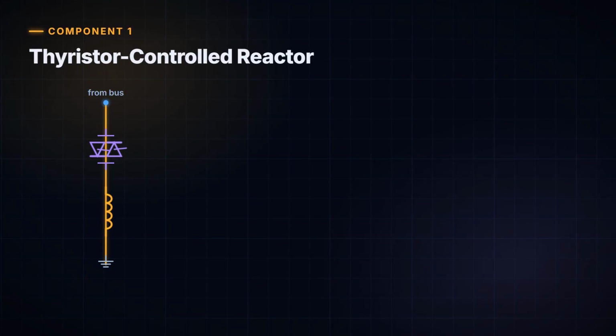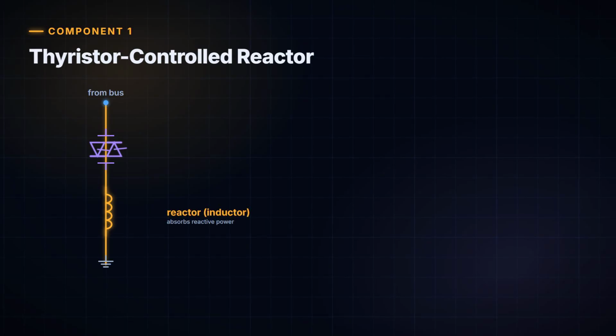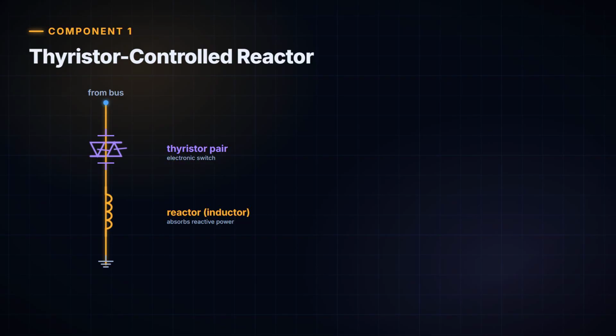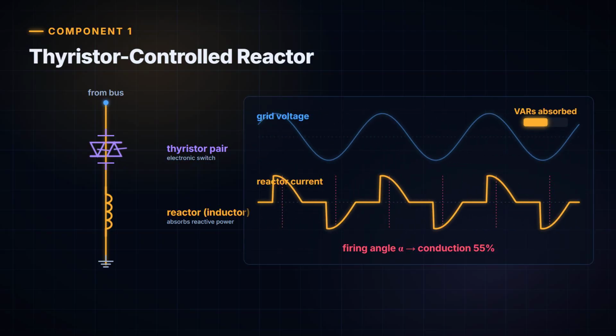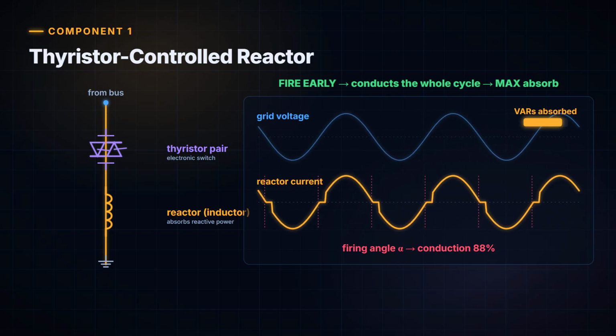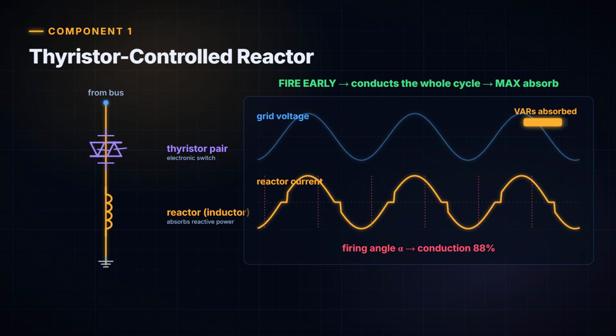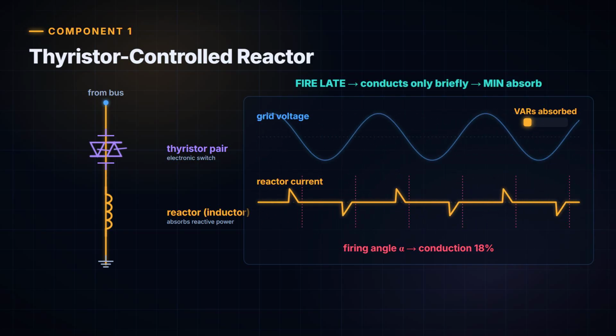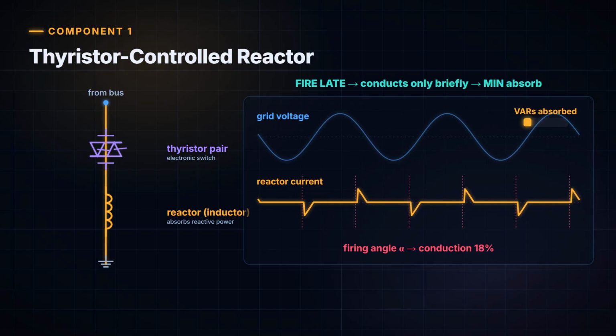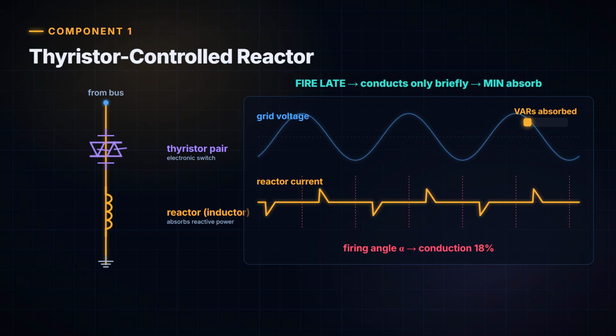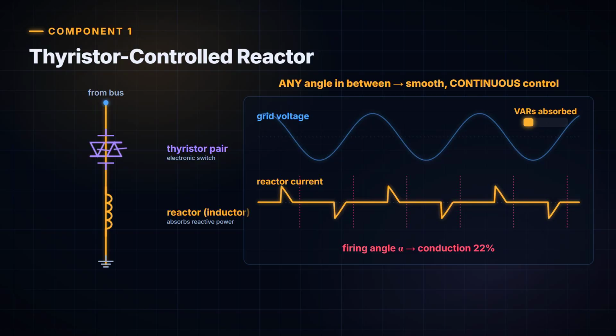Here's the thyristor-controlled reactor, or TCR. It's two things in series. A reactor, which is just a big inductor, a coil, and a pair of thyristors connected back to back. Now, a thyristor is essentially a high-power electronic switch. Once we trigger it, it conducts for the rest of that half cycle, and then naturally turns off when the current passes through zero. So here's the trick. By choosing when in each half cycle we trigger the thyristor, engineers call this the firing angle, we control how long the reactor is allowed to draw current. Fire early, and the reactor conducts for almost the whole cycle, absorbing the maximum amount of reactive power. Fire late, and it conducts only briefly, absorbing very little. And because we can choose any firing angle in between, the TCR gives us smooth, continuous control over how much reactive power we soak up.